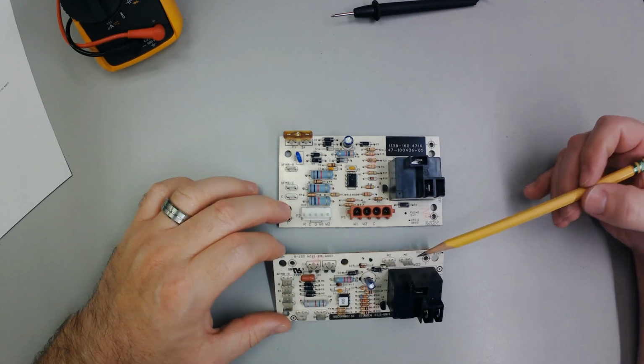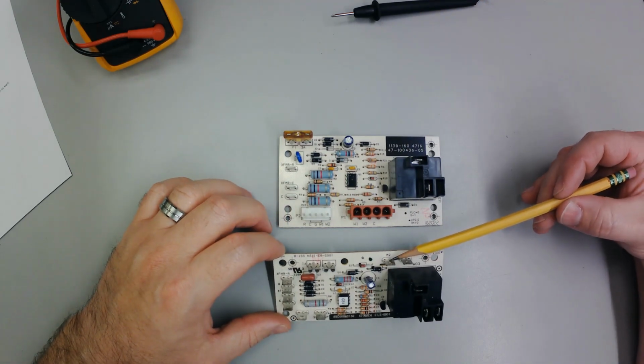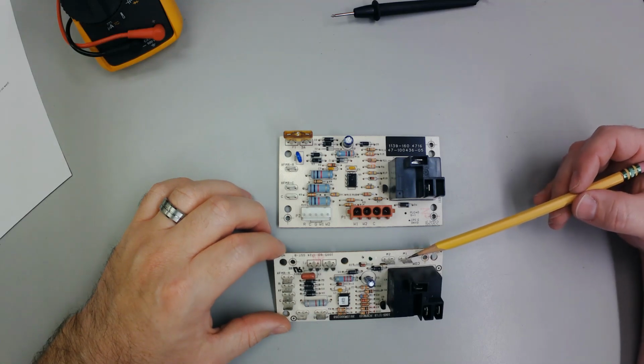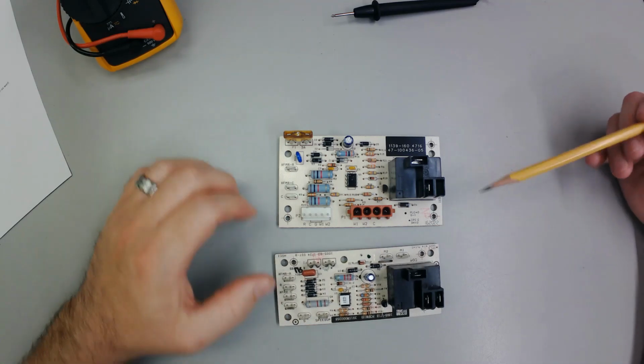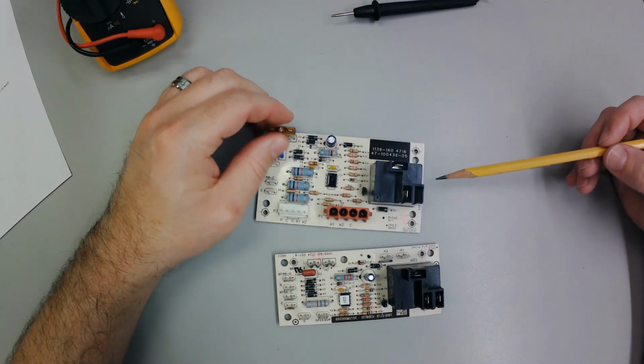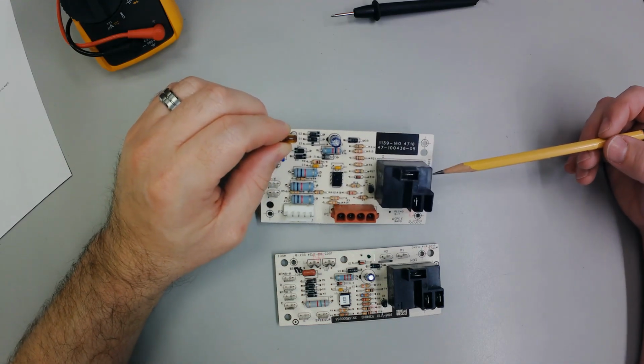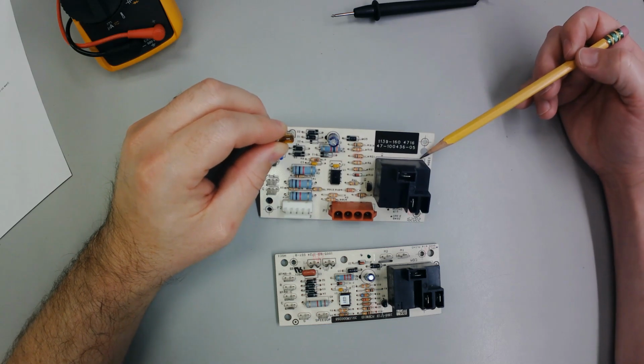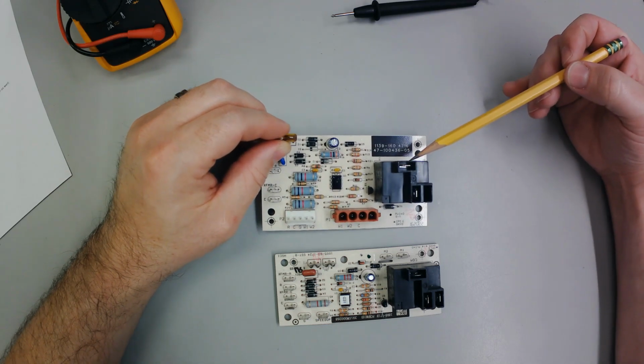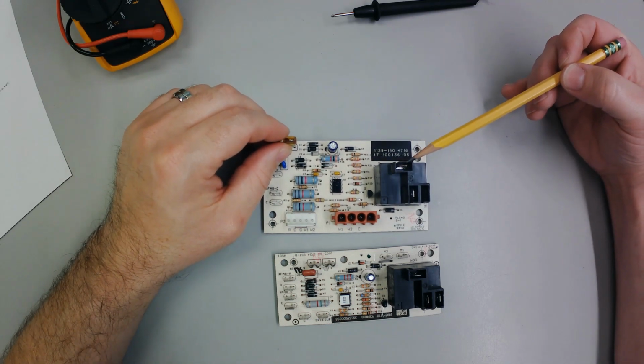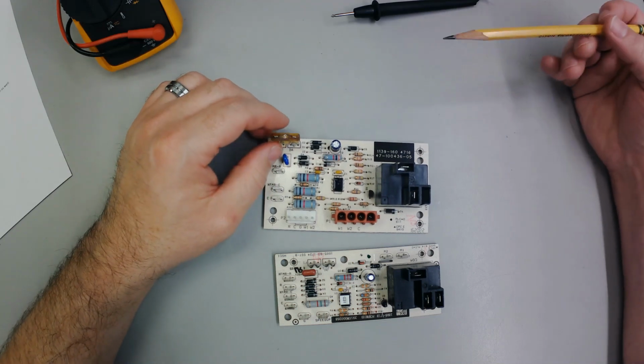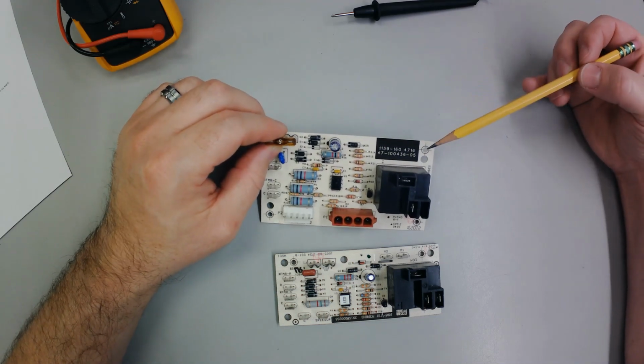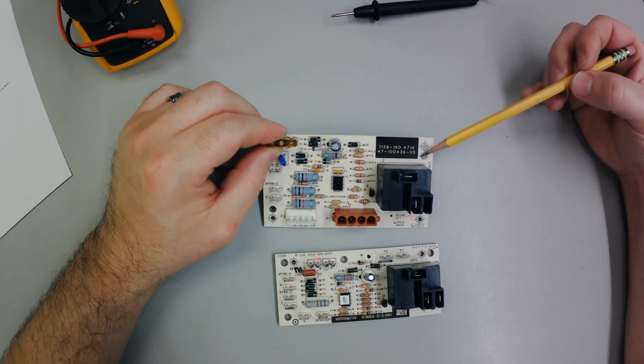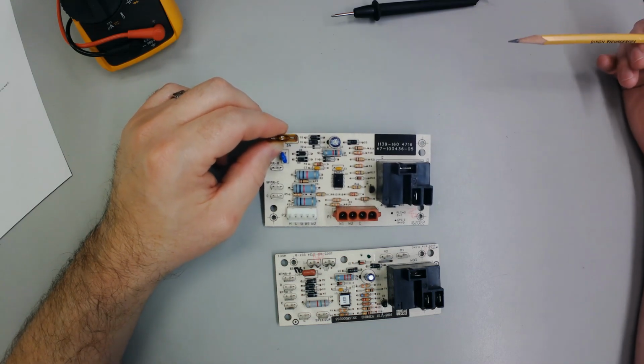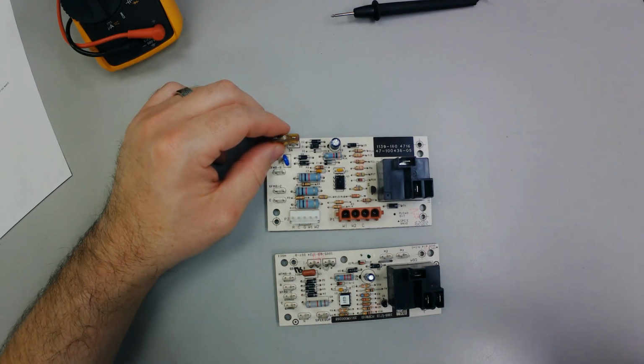With the fan stuff, you'll notice that there's also a couple park terminals that the Goodman has off to the side of their relay. You don't see that on this blower board. All right. So when we're not using, if I were to have high speed on this fan relay coming out and powering everything, what do we do with medium and low? On the Goodman, you had a place to put it, but on the Rheem, you don't. You just have to dress those up, zip tie them or cap them.